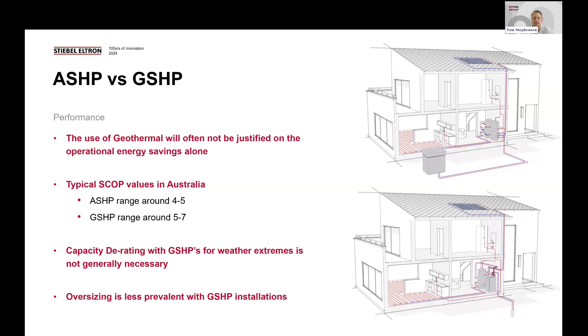Some other considerations when doing comparisons, bearing in mind if we're talking in a general heating and cooling sense, our heat emitters in the building will always be the same. We are talking about water-to-water heat pumps in the comparison versus air-to-water heat pumps. So leaving the DX side alone for this presentation, if we've got a water distribution in the building, the infrastructure is going to be the same, whichever the solution is. Generally, as a typical statement, we'd say that air source and ground source will be very similar in cost for the same capacity. The only exception in terms of comparison in cost is going to be the installation. You've got plumbing on both sides. And then furthermore to that is then the cost of where are you getting that source from. So if it's a conventional closed loop ground heat exchanger, if it's a water-based heat exchanger, be it open or closed loop, and that's the variable figure.